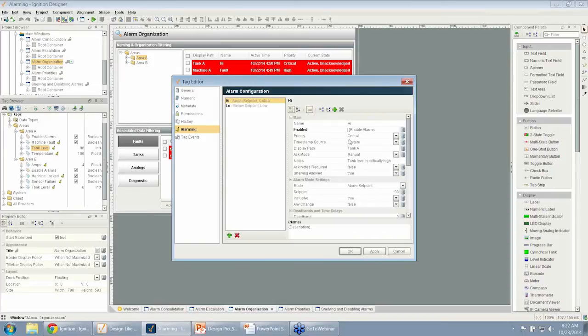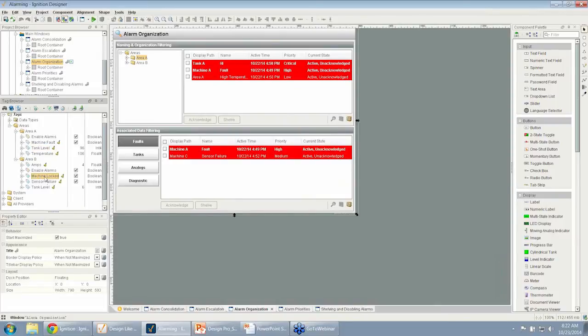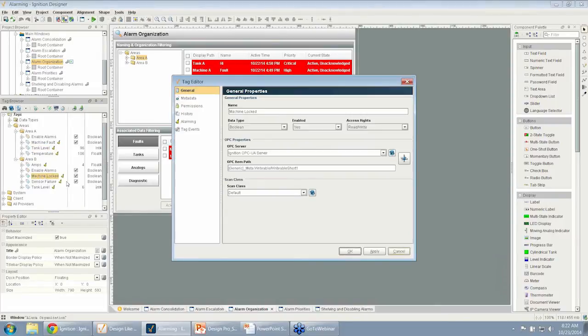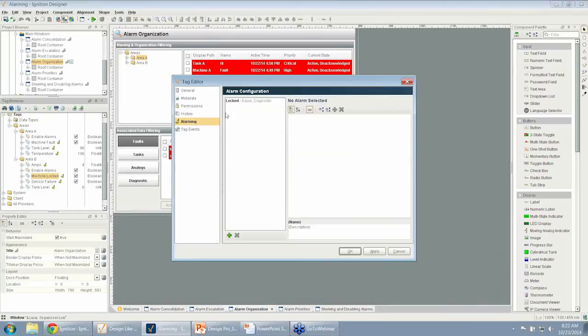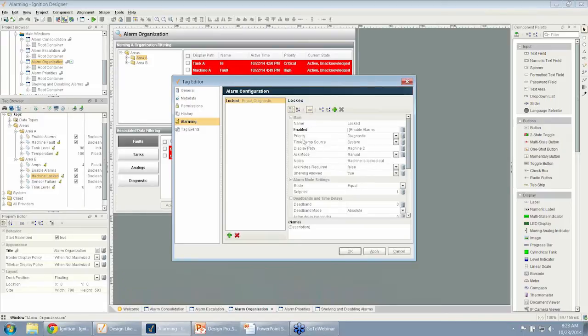I have one at the very bottom, let's say a machine's locked out, maybe a lockout tagout type procedure. If I look at that and go to the alarm, I do want to see that information somewhere. It's not that I don't want it in the system, I just don't want to use it for alarms that are going to get notified. I just want to use it for diagnostic purposes, for troubleshooting purposes. So I've put the priority here to diagnostic, and we could filter those out.